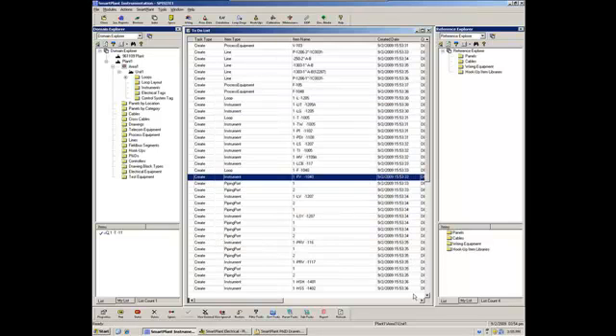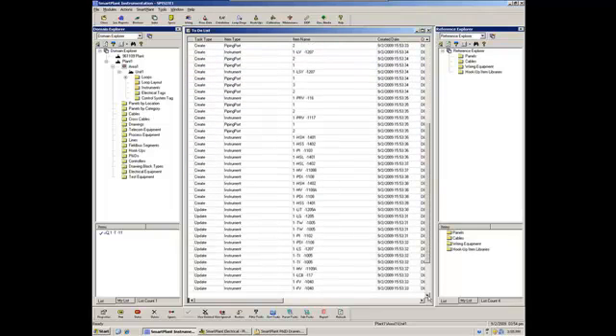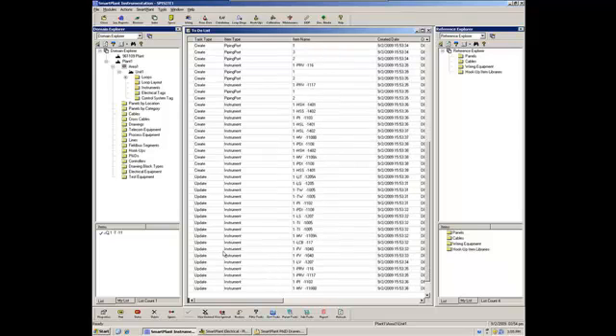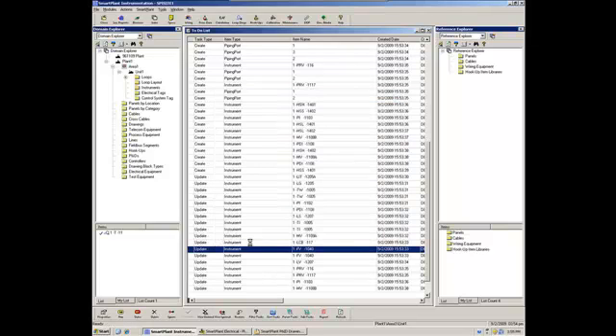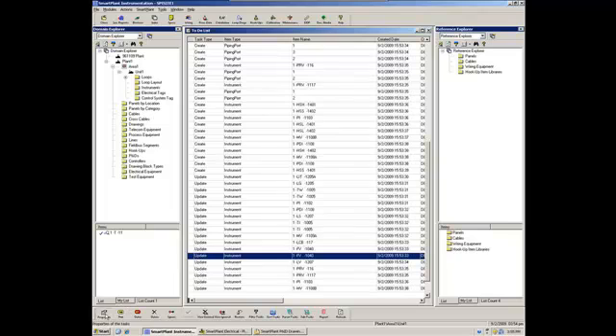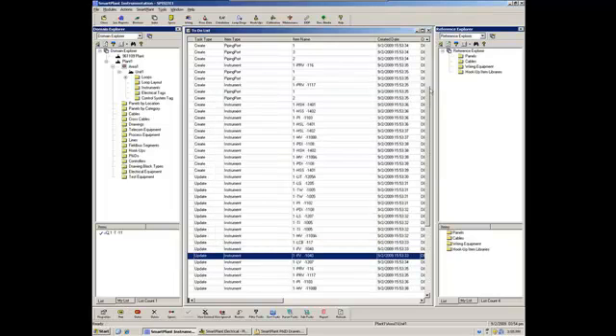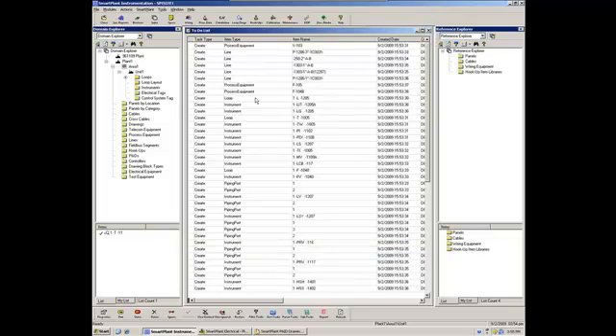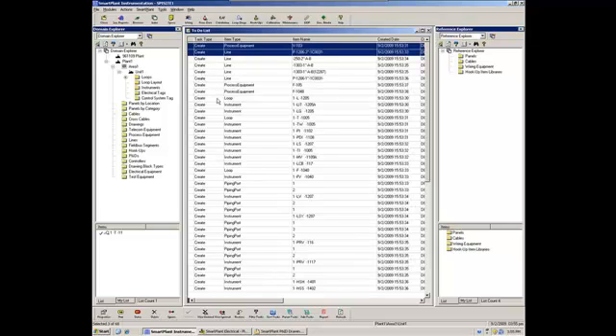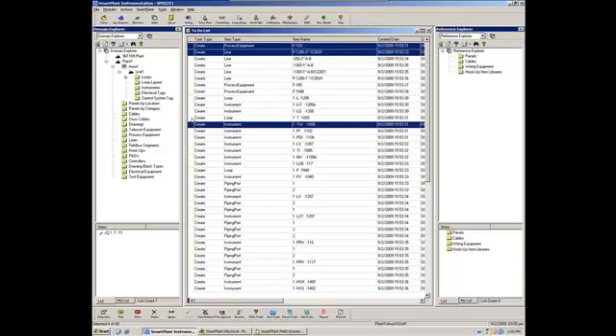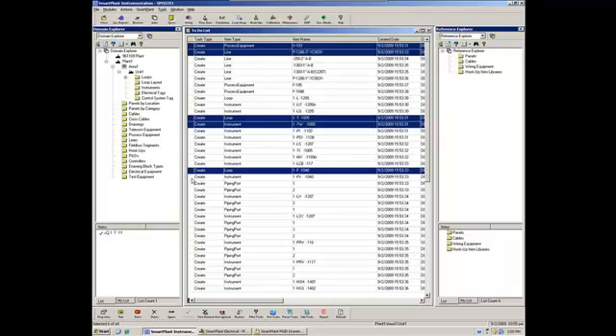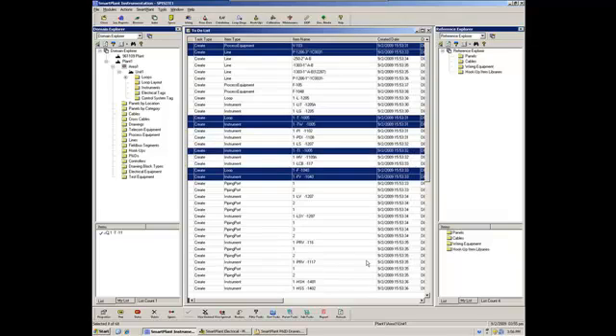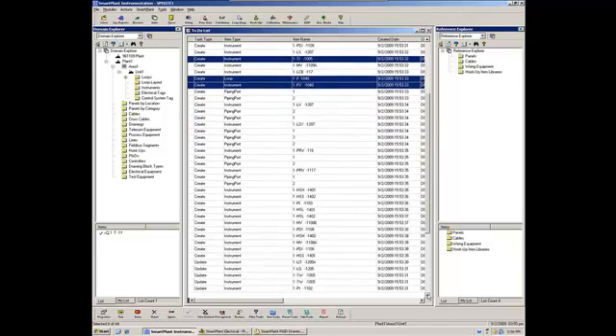So then we have a couple of update tasks for the same instrument. So if we locate the instrument in the to-do list, and we click here in update, this is just to assign the loop to the instrument. And the other one is to assign the line to the instrument. So I won't execute the whole to-do list. I will just select what I need right now for the demonstration. So I will select the process equipment, the line. I will select the couple of instruments that I want to show you. So create this instrument, this loop. Of course, the loop I just created for the demo, the change we did in the P&ID, the control valve. I will select the temperature indicator here. Let's go down and select some of the data.